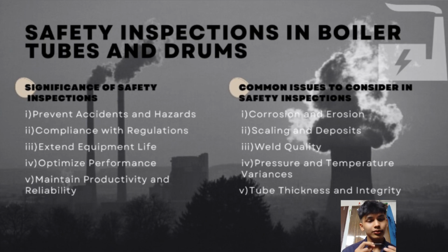While the third common issue is weld quality. Welds in boiler tubes and drums are critical for their structural integrity. Inspections should evaluate the quality of welds to ensure they meet specified standards and are free from defects. Then after that, pressure and temperature variances. Monitoring and verifying that pressure and temperature levels are within safe operating limits is crucial to prevent overpressure incidents or excessive temperature conditions that could compromise boiler safety. Okay, the last point for common issues is tube thickness and integrity. Checking the thickness of boiler tubes and assessing their integrity through non-destructive testing methods are essential to identify thinning or weak areas that could lead to failures.